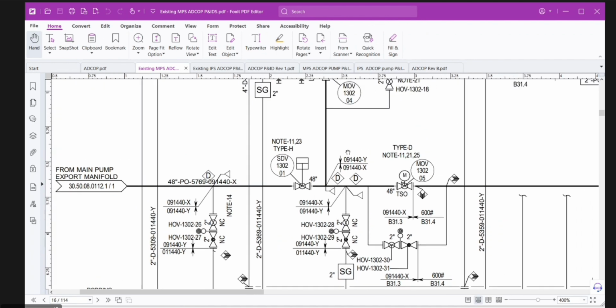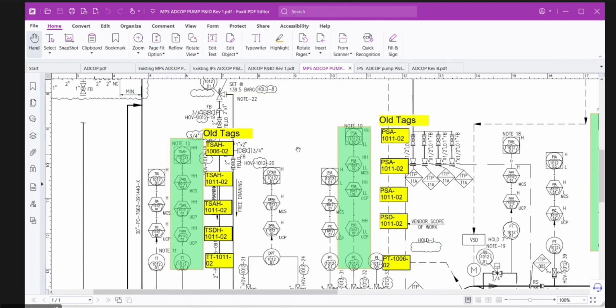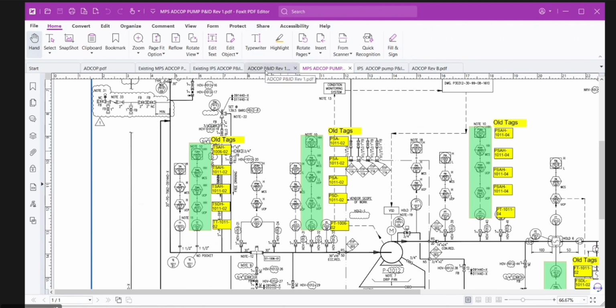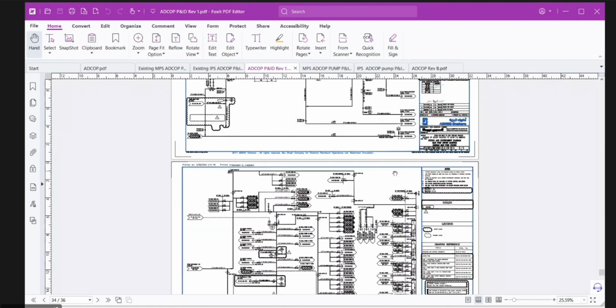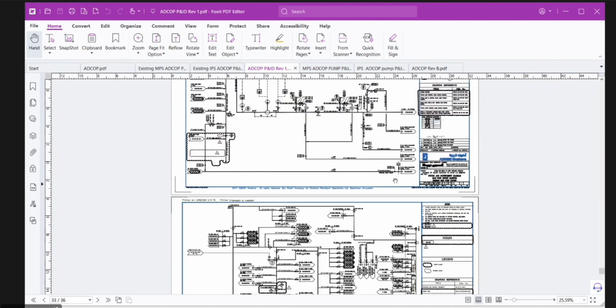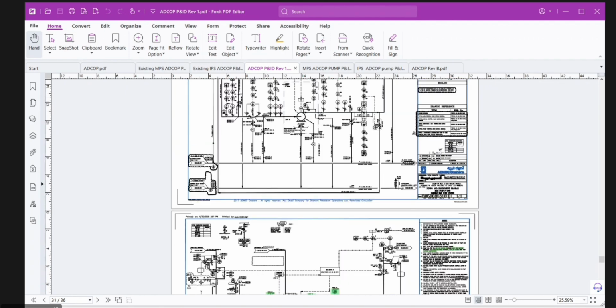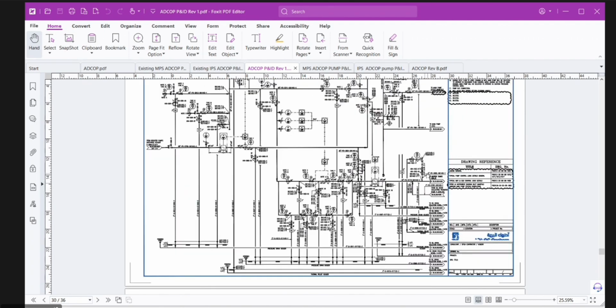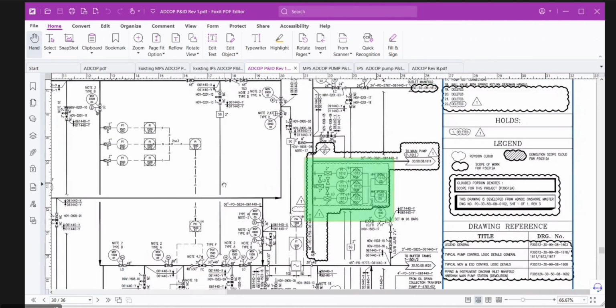Okay. So guys, please bear with me, I just want to refresh it. On 70% flow, it will trip the entire system, ESD2. And on high pressure on an individual pump, this will trip the individual pump. So these are two independent functions and independent safeguards. So I have taken credit of SIS1 for this case also, considering that this is SIL2.